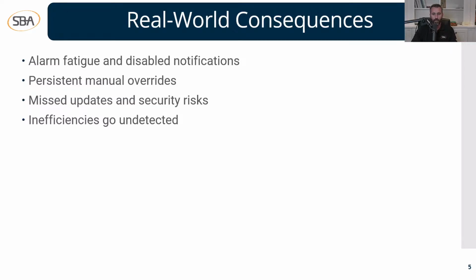Equipment fails prematurely. This is a big deal too, from lack of proper scheduling or maintenance. This can also tie into the sequence. Maybe there wasn't a rotation on the boiler or pump rotation, so you're just running those pumps all the time when you only really need one. You're wasting energy there. And maybe you're running your chiller too much. Maybe you can shut that down every once in a while, or rotate a chiller or rotate a boiler, and instead you're just running them all the time.